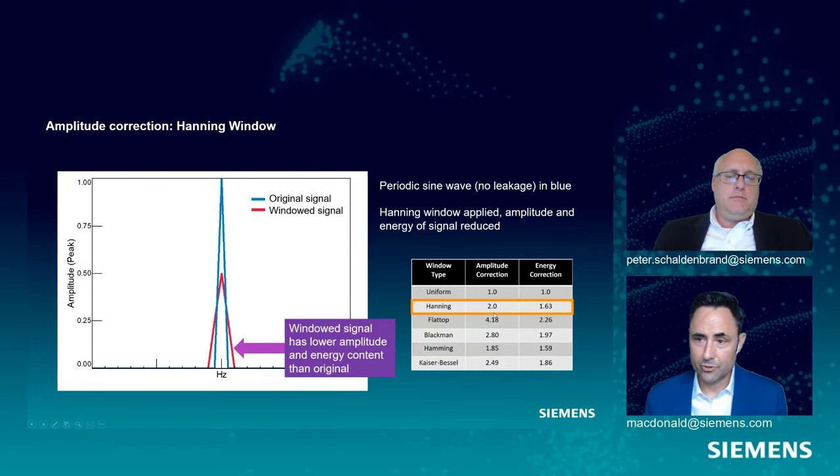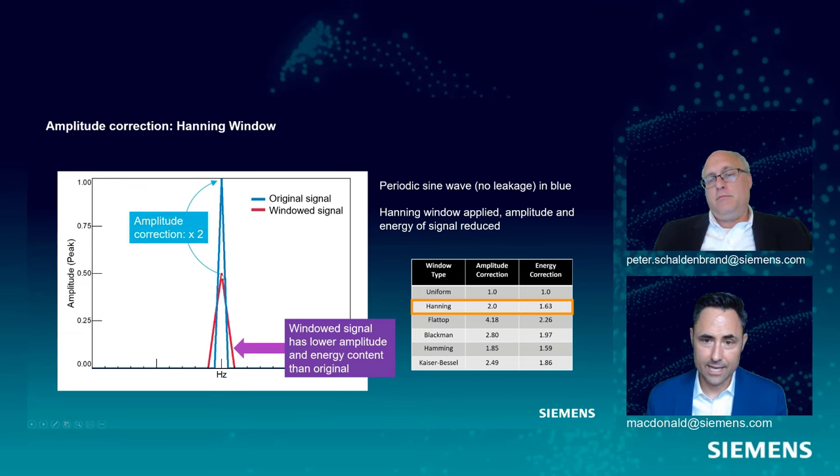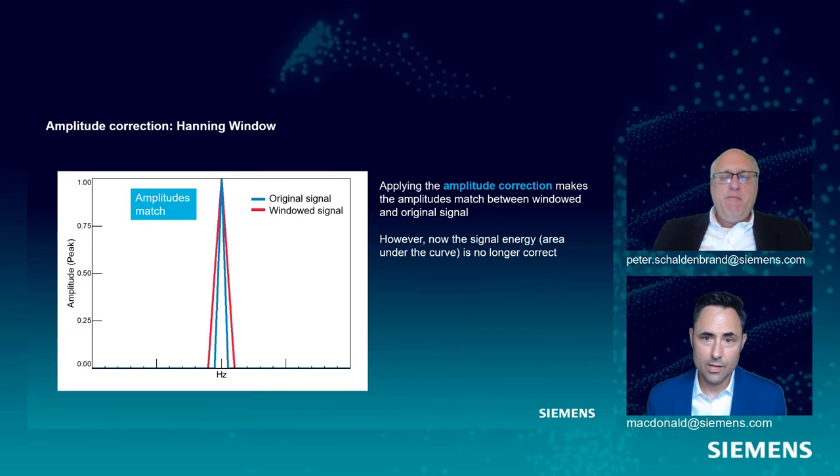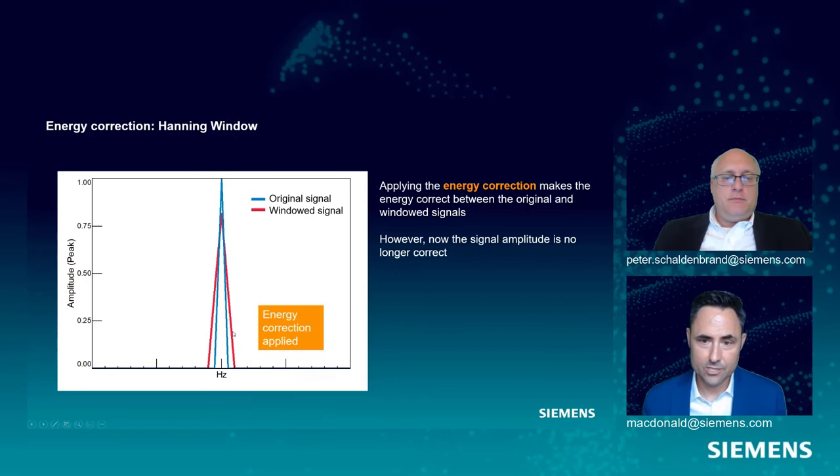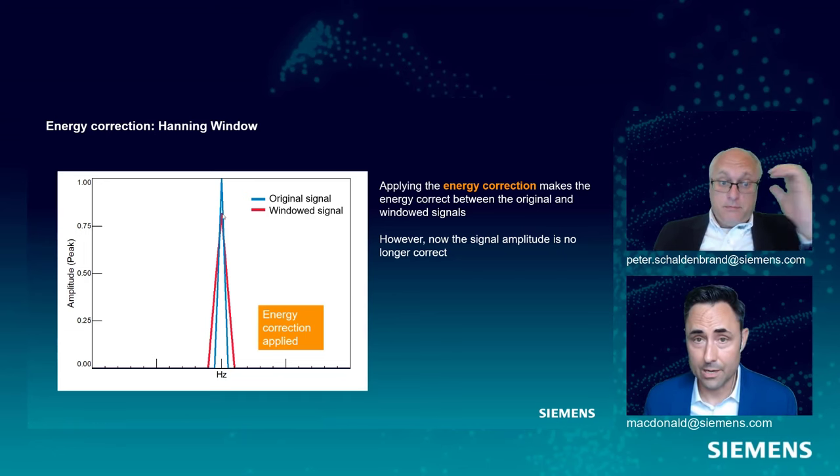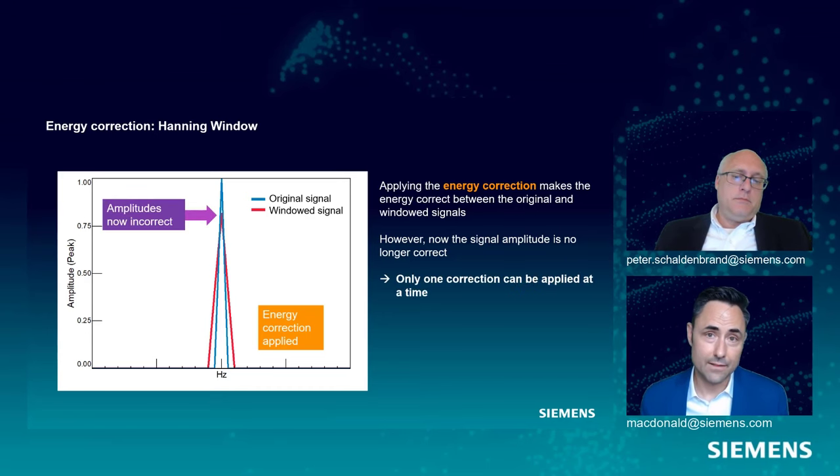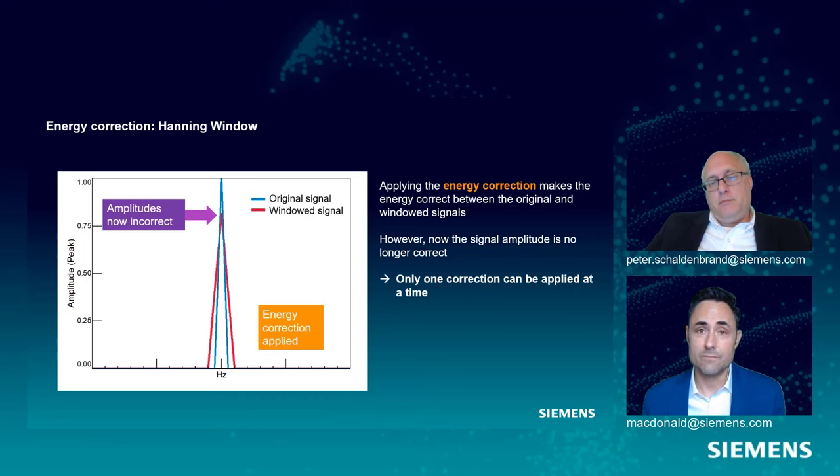The nice thing about these windows is the amplitude correction and the energy correction are known values because we knew what the window functions were going in. We can calculate the effects on amplitude and energy, and so we can counteract that. So for our Hanning window example, we see our amplitude correction is 2, so you see our amplitude is exactly half. So if I want to correct for that, I just multiply my amplitude by 2, and boom, I've got my amplitude perfectly corrected. You'll notice my energy is still not quite exactly right. It should be looking like the blue, so now let's do an energy correction. Energy correction is 1.63, and so I can correct for the energy as well. So here the energy or the area under the blue curve is identical to the area under the red curve. You see I had to bring this amplitude down a little bit in order to correct that energy error. The only bad thing about window corrections is that they cannot be both applied at the same time. We can correct either the amplitude or the energy, and it's really left up to us as an engineer or the tester to make this decision and apply one of these corrections.